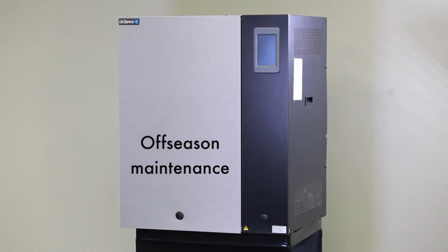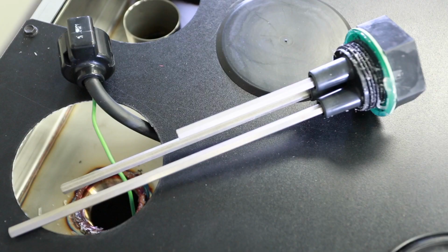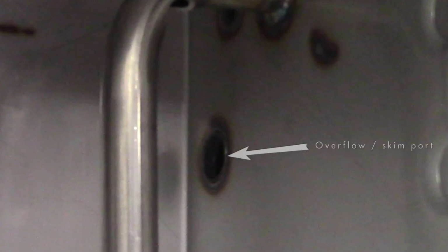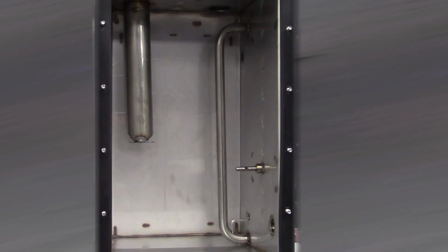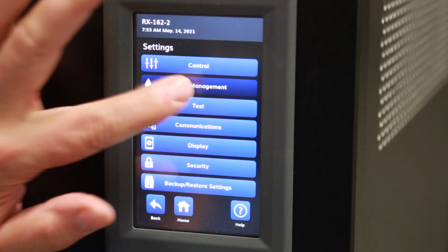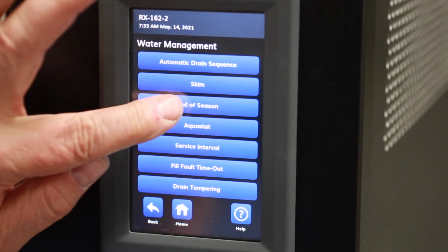For off-season maintenance, perform complete inspection and cleaning of the following: heaters, probe rods, skimmer port and water seal, and the humidifier tank. After cleaning, the humidifier should remain empty until humidification is required. Before you head to the site, here are some things you should verify. The unit can be shut down long enough for maintenance to be completed, and that the maintenance location for the unit is clear and ready.